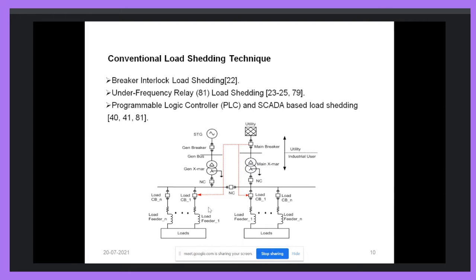Whenever this circuit breaker is disconnected, the load circuit breakers will automatically be disconnected. Okay, so it makes no difference whether the requirement is there or not. These loads will be automatically disconnected whenever the utility grid breaker is disconnected. So in this case, always a greater amount of load will be disconnected. So this load shedding is not appropriate.